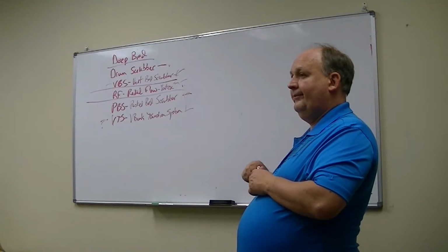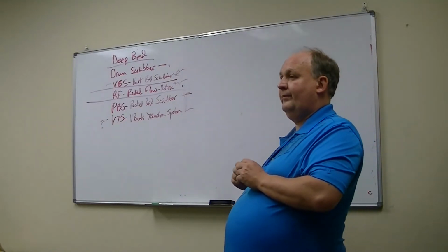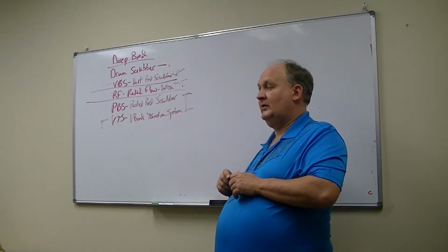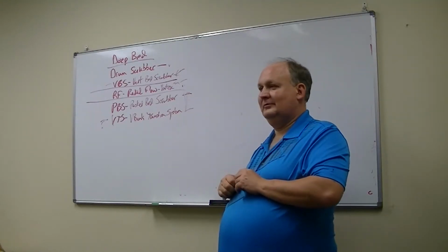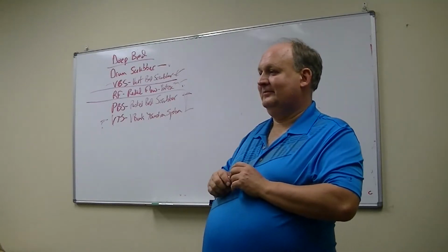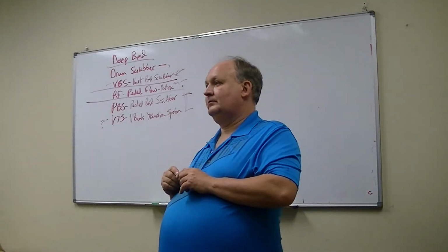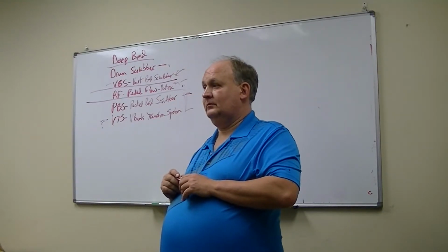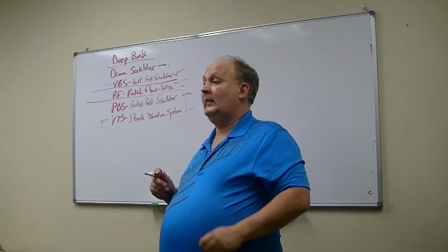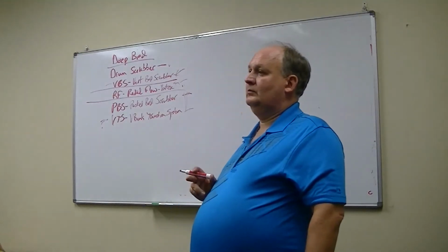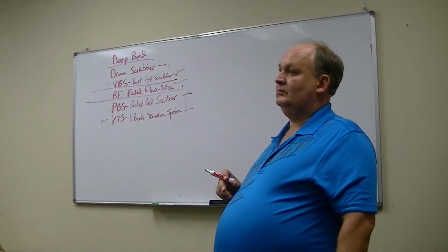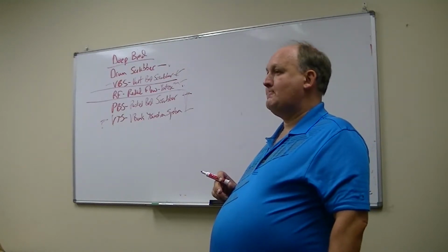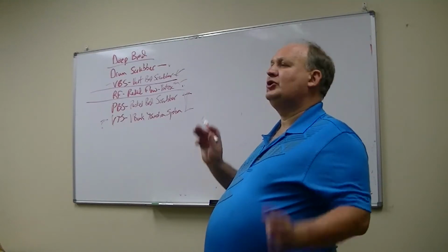All right? We had an incident today where an engineer had requested 12 inches of water column. And it's like, okay, what's up with this? We can just say, yeah, you can get that, or we can say, well, here's what we're going to have in our system. You need all this extra 8 inches on your end, or else. So sometimes we need to clarify that. I've actually had them ask for 25 inches of water column before, which is crazy. They're just thinking, oh, more must be better. So they say, well, we'll just allow for extra.